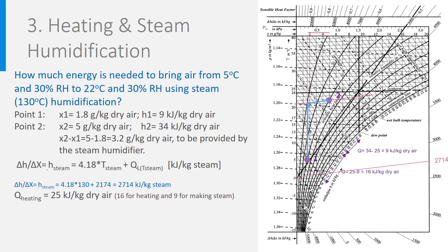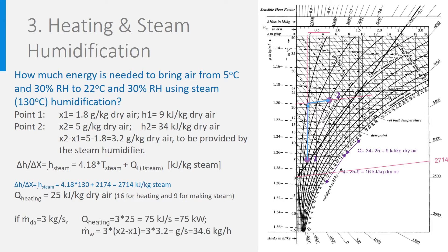With 3 kilogram per second flowing, this leads to a heating capacity of 75 kW and a mass flow rate of 34.6 kilogram per hour. Note that the total energy needed is identical for adiabatic and steam humidification and depends only on the start and final states. However, this heat is divided differently depending on the chosen process. Be also aware that the energy needed to make the steam is included in these calculations.